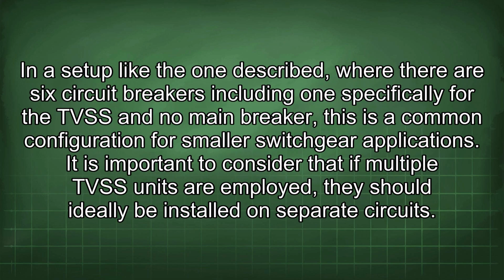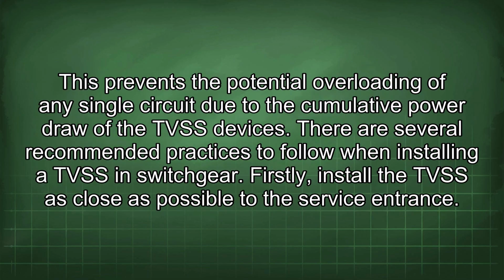This circuit breaker provides the necessary power to the TVSS and protects it from overcurrent conditions. In a setup like the one described, where there are 6 circuit breakers including one specifically for the TVSS and no main breaker, this is a common configuration for smaller switchgear applications. It is important to consider that if multiple TVSS units are employed, they should ideally be installed on separate circuits. This prevents the potential overloading of any single circuit due to the cumulative power draw of the TVSS devices.